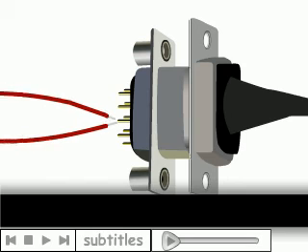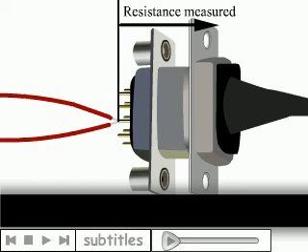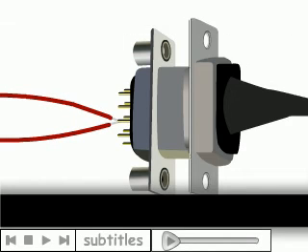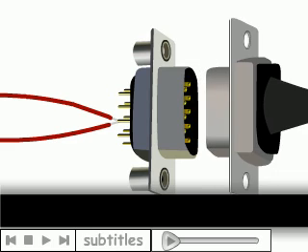Actual resistance measurements take place after the point where the force and sense wires come together. So a 4-wire fixture that uses a mating connector will still include the resistance of the mating pins, usually 10 to 100 milli-ohms.